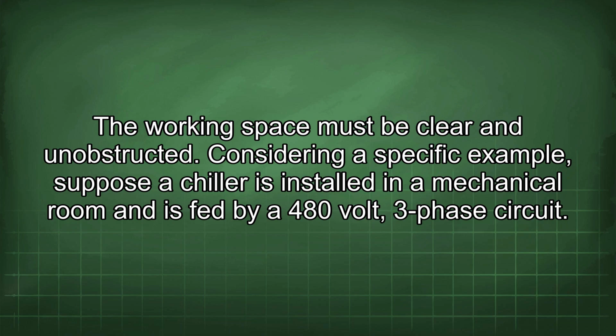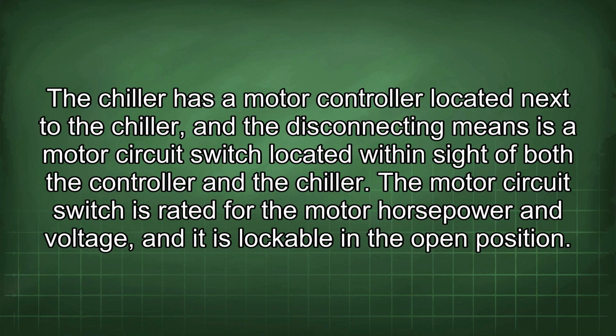Considering a specific example, suppose a chiller is installed in a mechanical room and is fed by a 480-volt, three-phase circuit. The chiller has a motor controller located next to the chiller, and the disconnecting means is a motor circuit switch located within sight of both the controller and the chiller. The motor circuit switch is rated for the motor horsepower and voltage, and it is lockable in the open position.